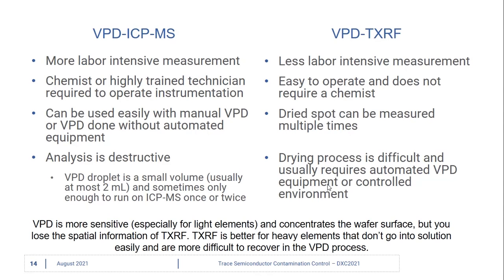When comparing VPD ICP-MS with VPD TXRF, generally the ICP-MS measurement is considered more labor-intensive and requires a chemist or highly trained technician compared to TXRF. Also, VPD ICP-MS can be done manually without automated equipment. However, the analysis is destructive and the VPD droplet volume is small, so sometimes you can only get one or two runs of the droplet on the ICP-MS.